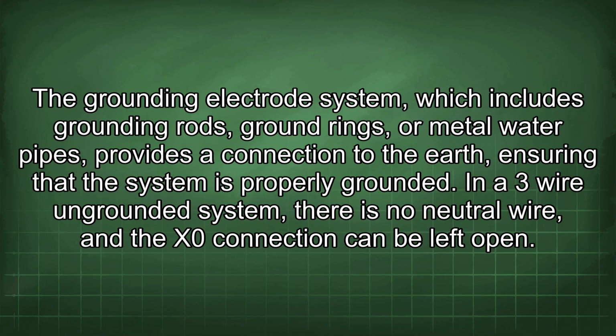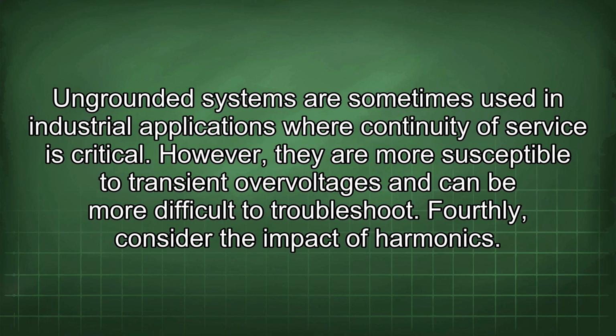The grounding electrode system, which includes grounding rods, ground rings, or metal water pipes, provides a connection to the earth, ensuring that the system is properly grounded. In a 3-wire ungrounded system, there is no neutral wire, and the X0 connection can be left open. Ungrounded systems are sometimes used in industrial applications where continuity of service is critical. However, they are more susceptible to transient overvoltages and can be more difficult to troubleshoot.